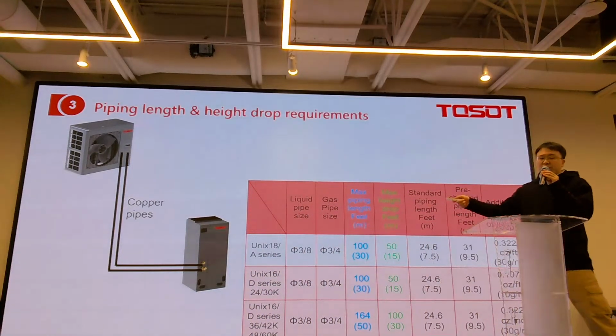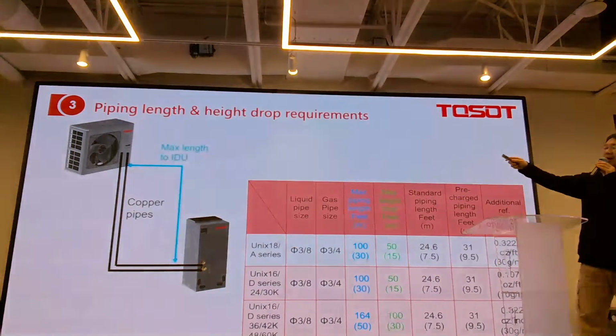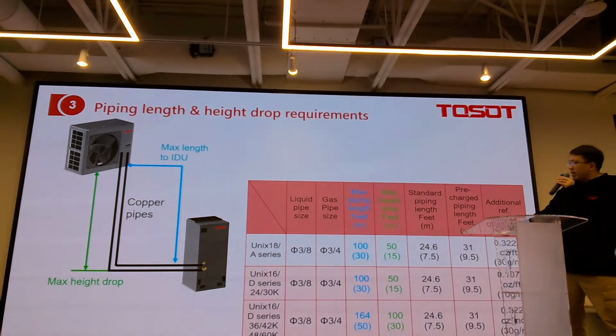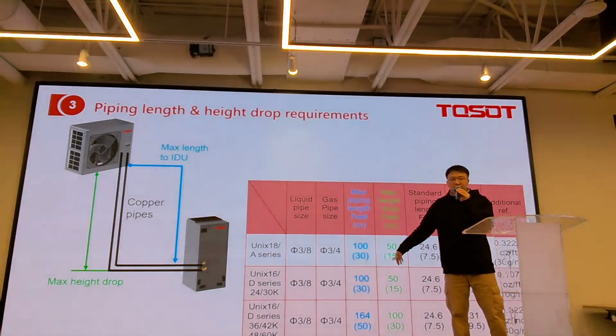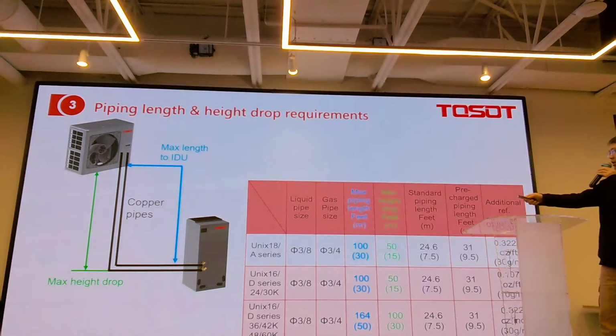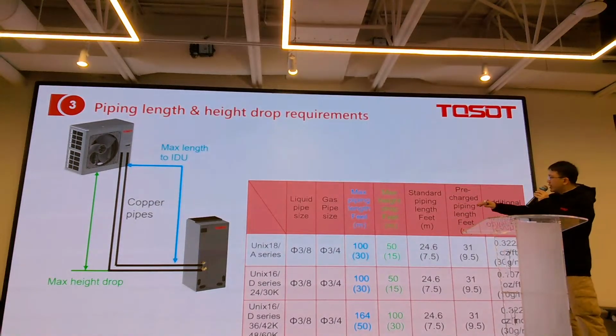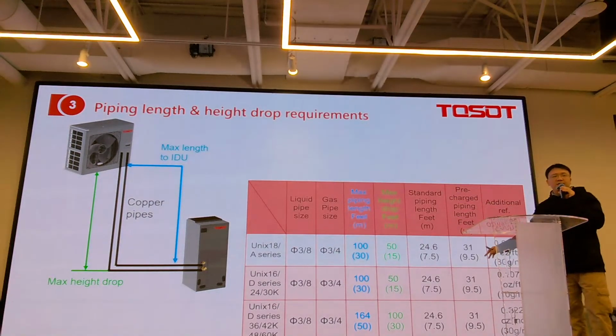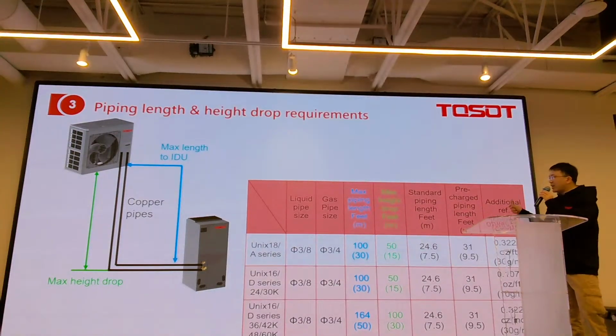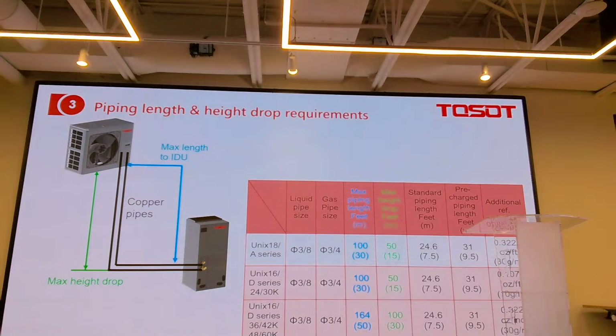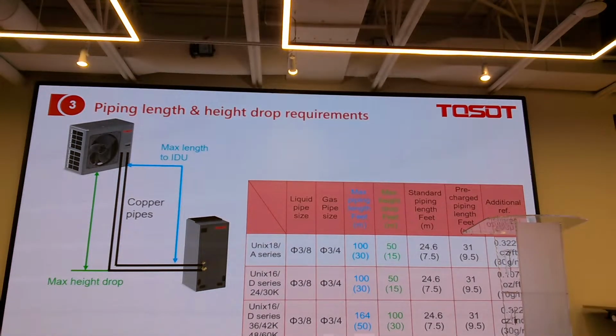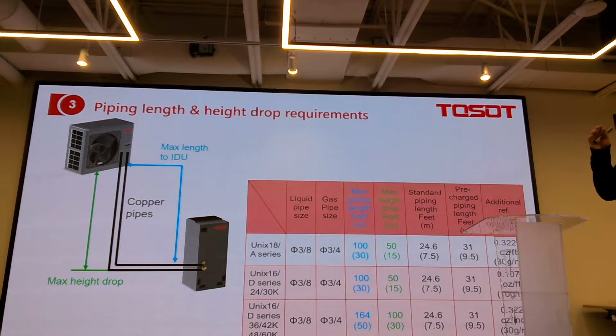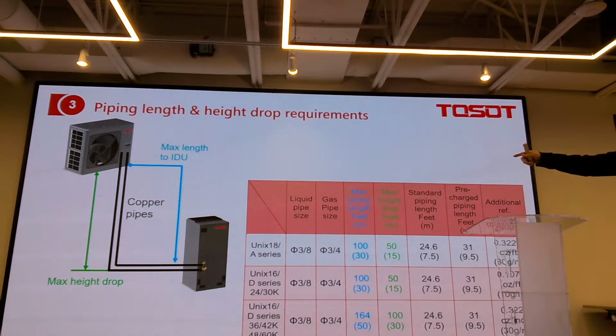We have a limit about the total piping length and also the height difference. Make sure you are within this range. The pre-charge range is 30 feet. Within 30 feet, no need to charge anything. Longer than that, charge an additional amount. What happens if it's short? Short is okay. The minimum is 3 feet. You don't have to take it out every time? No need. Which means if your line length is within 30 feet, no need to do anything. Just vacuum the copper tube. Okay.